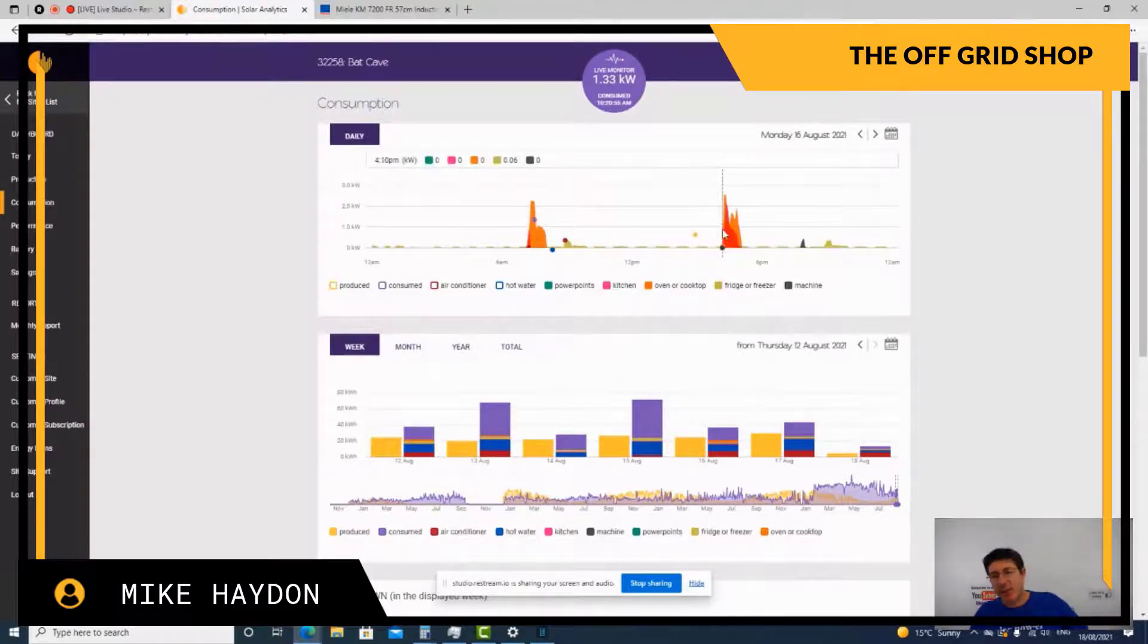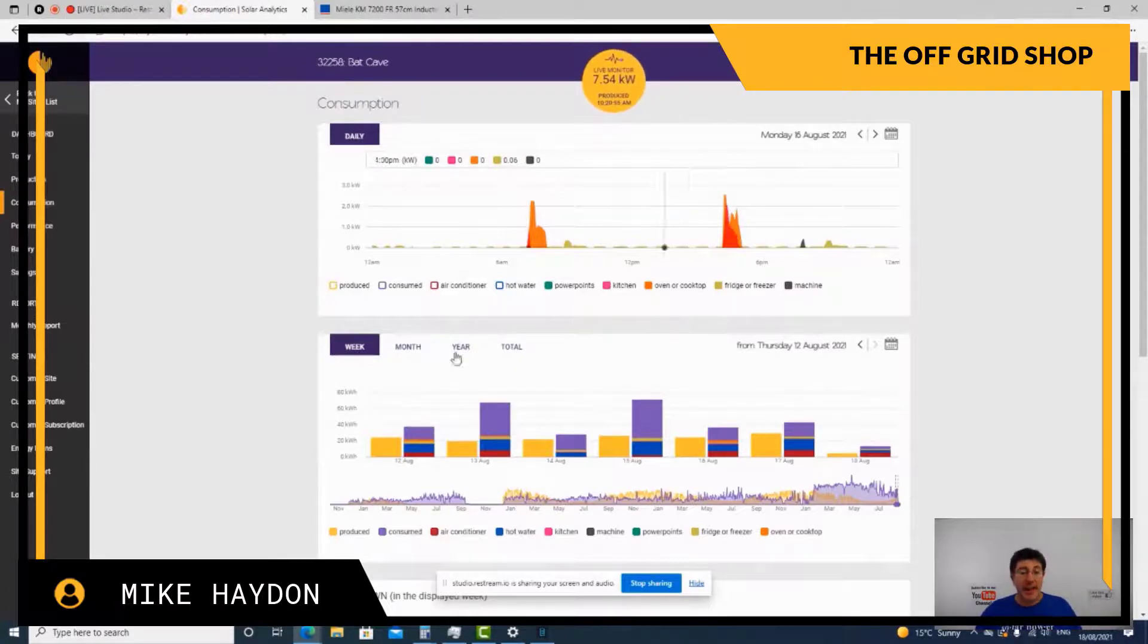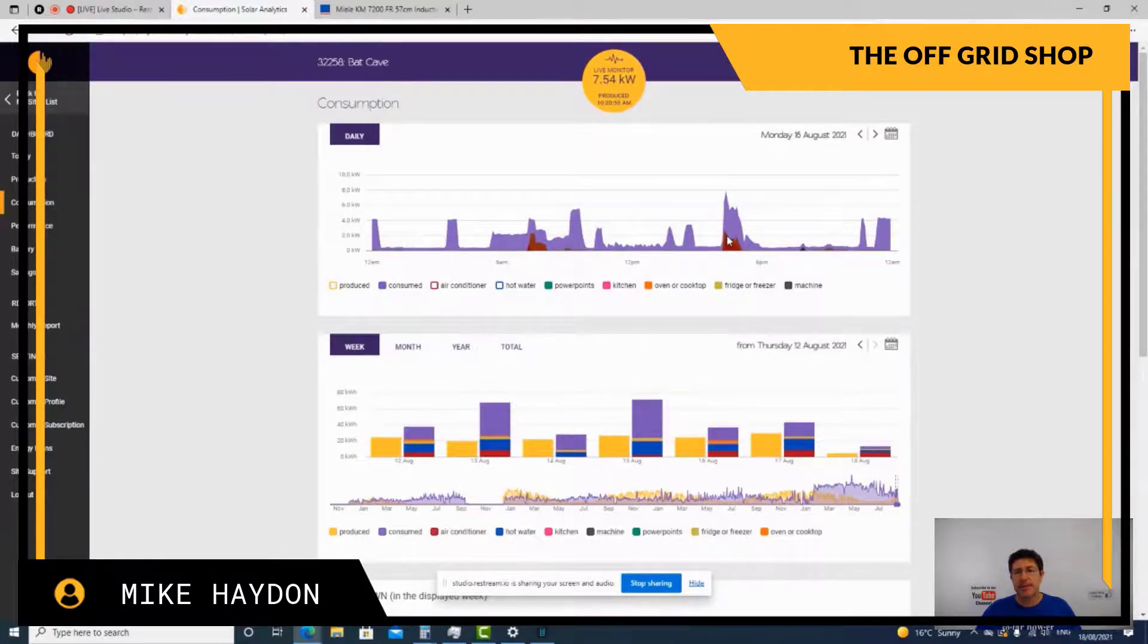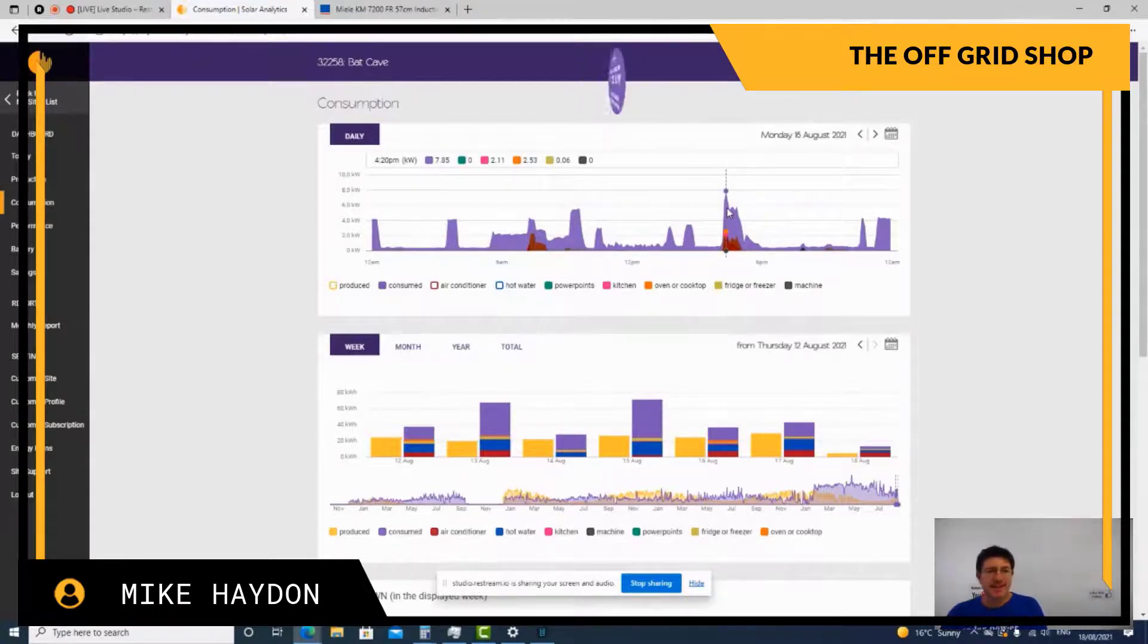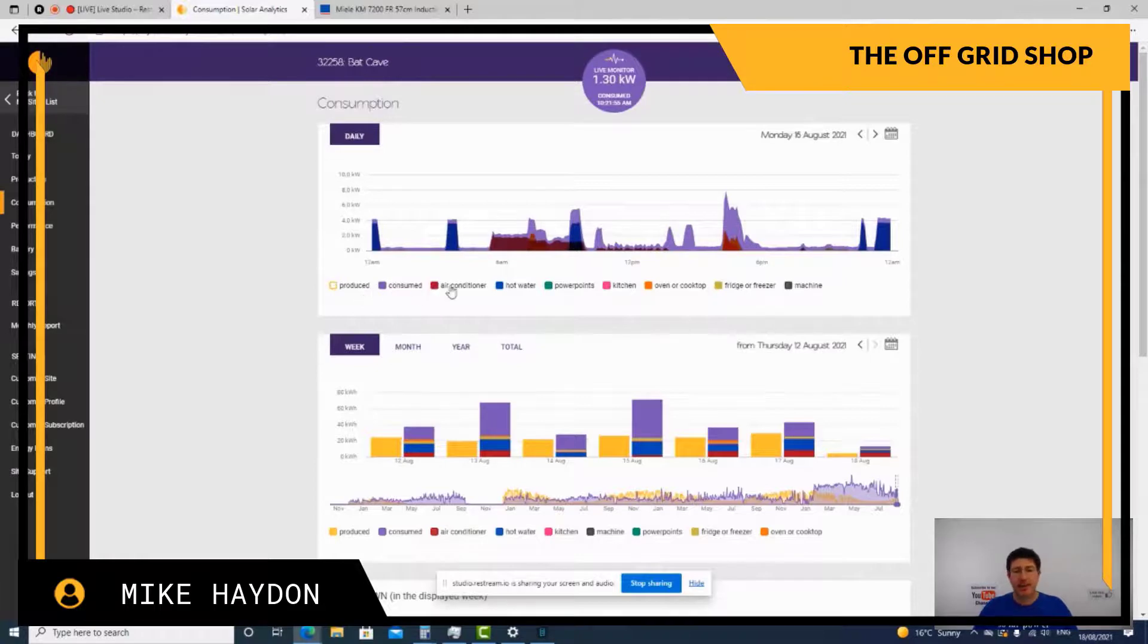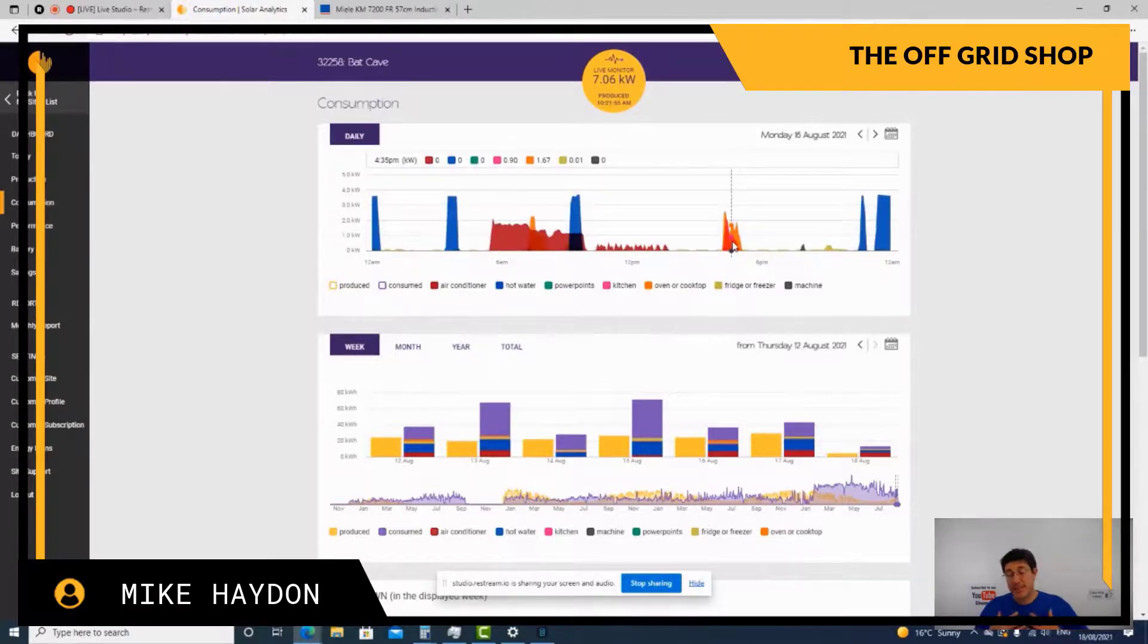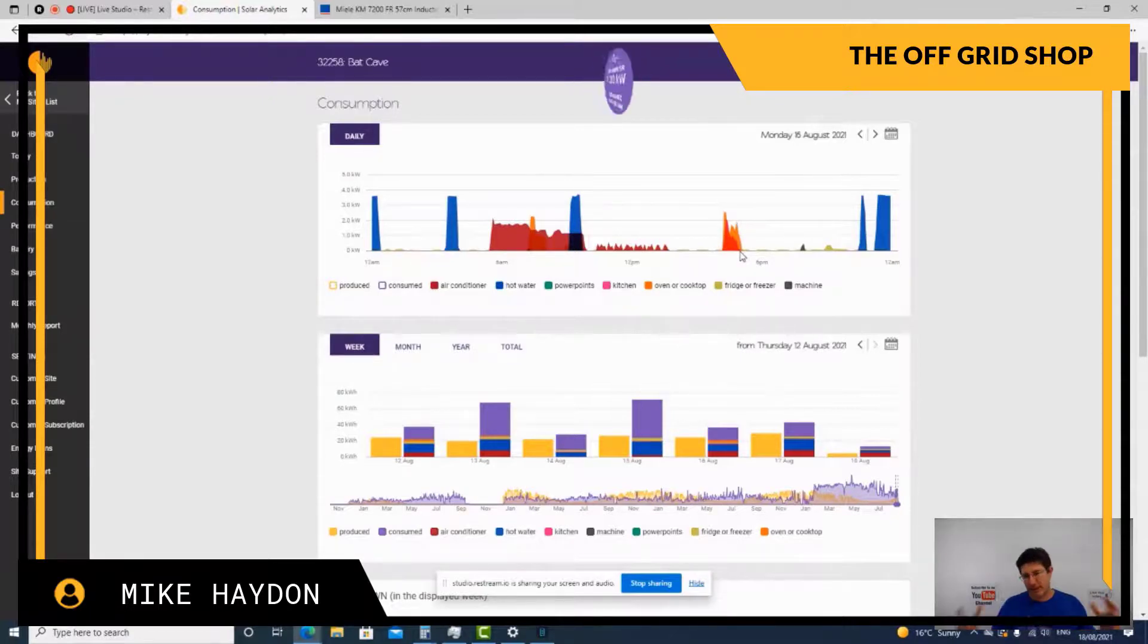So as you can see that if when you are cooking more things, you've got your main meal in the oven, you've got your mashed potato in one pot, then your peas in another pot, you're cooking, you've got all three devices working. And in this situation, my house, we'd be requiring at this point in time, at that spike. Probably plugged the car in. This is an electric car getting charged for this amount of energy at my house. So for me, in my situation, we'd actually require an eight kVA inverter in that moment, probably wouldn't cut the mustard. We'd be looking at more 10 or 15 kVA inverter to be able to run all that stuff at once. And look, very rarely have people out there got off electric cars off grid. And if I was off grid, I'd be charging my electric car of a day, not doing it when I get home plugged in over an afternoon.